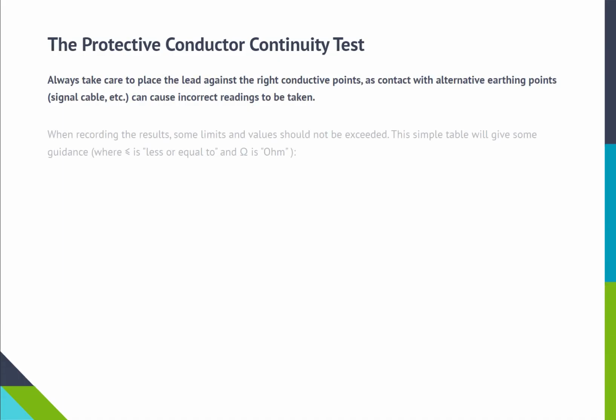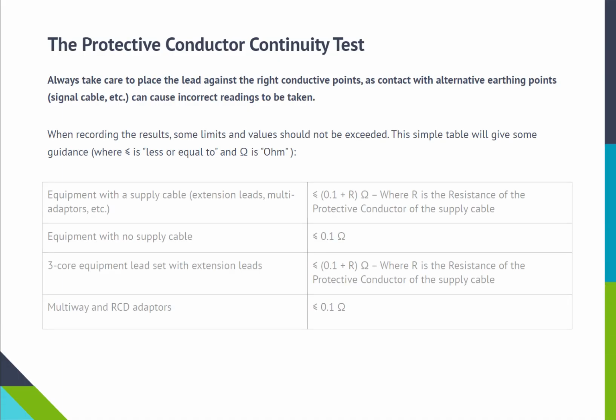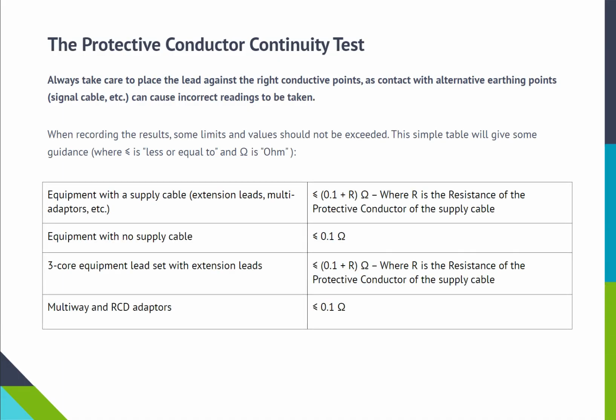Always take care to place the lead against the right conductive points, as contact with alternative earthing points, signal cable, etc. can cause incorrect readings to be taken. When recording the results, some limits and values should not be exceeded. This simple table will give some guidance, where the sign is less than or equal to, and omega is ohm.